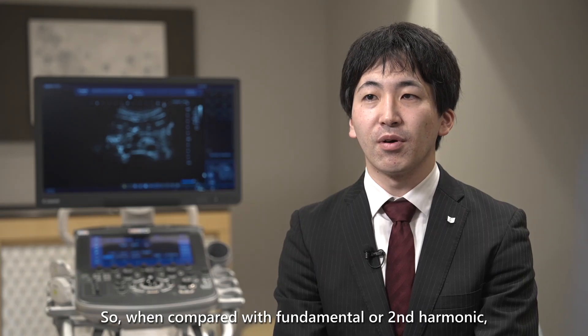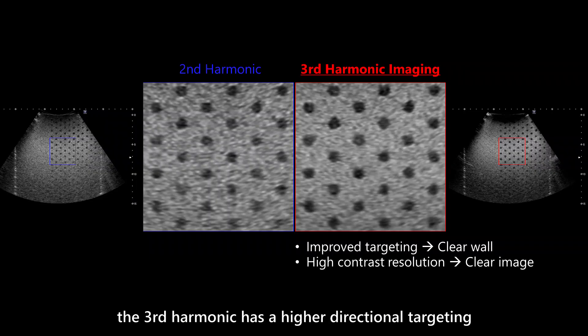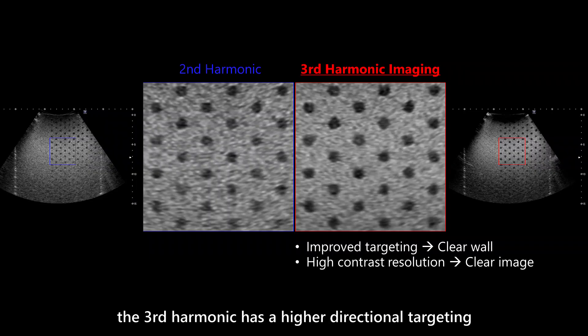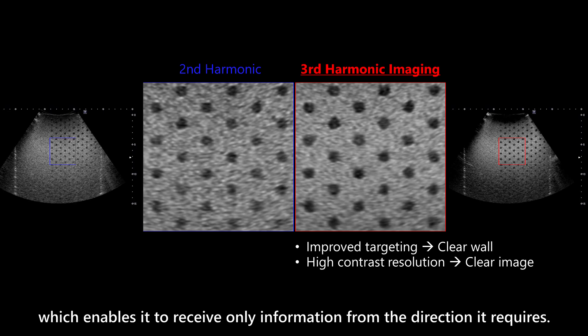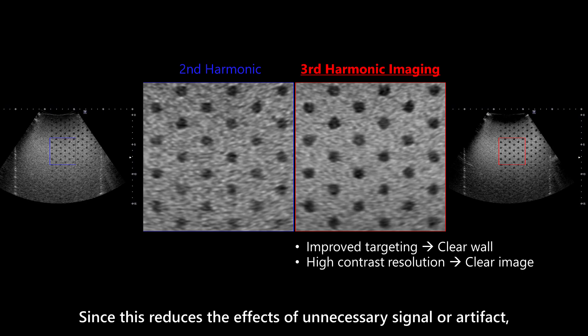When compared with fundamental or second harmonic, the third harmonic has a higher directional targeting, which enables it to receive only information from the direction it requires. Since this reduces the effects of unnecessary signals or artifacts, we are able to visualize the black areas clearly and show more edge detail.